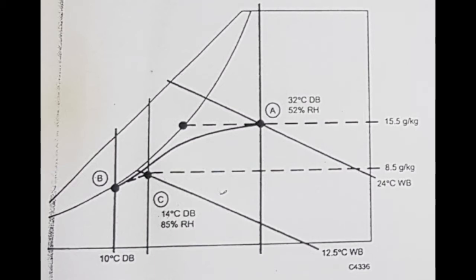Point number one: The entering condition of air is 32 degrees centigrade dry bulb and 52 percent RH, that is point A. The moisture content is 15.5 grams of moisture per kilogram of dry air, as you can see in the chart.